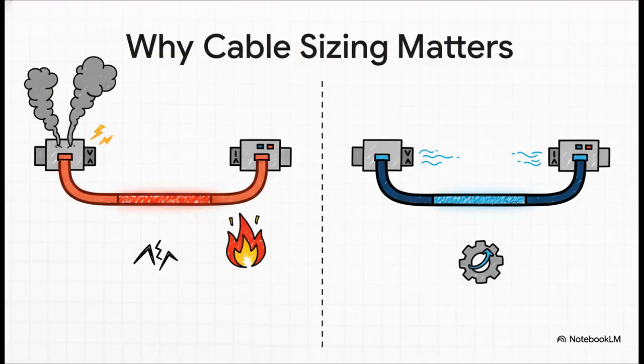That mindset starts with the absolute basics, like getting the cable size right. I know it sounds like a tiny detail, but using the wrong size wire is a recipe for disaster. It can overheat, and that's a huge fire risk. Getting the size right means the cable can handle the full load, all day every day, without breaking a sweat. It even accounts for the way voltage naturally drops over long cable runs.